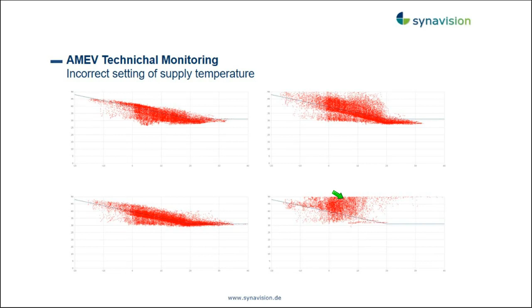This is an example of a detail we often found in big chiller plants or heating plants with triple or double pumps. Especially in triple pumps, you often have pumps working alternately - one pump working, then it stops, then it's working again and stops, while the other pump stops and starts working, stops and works.